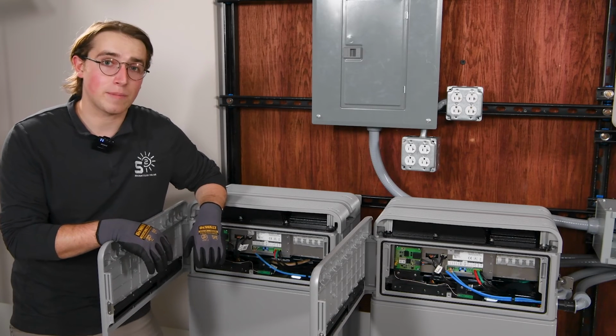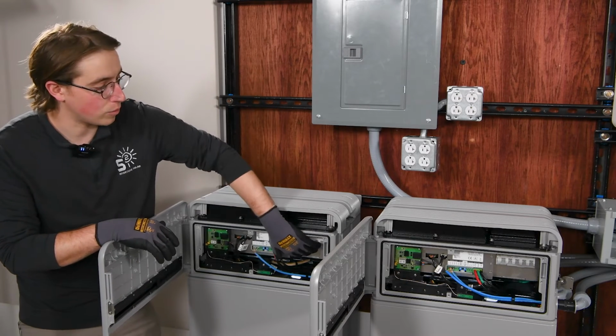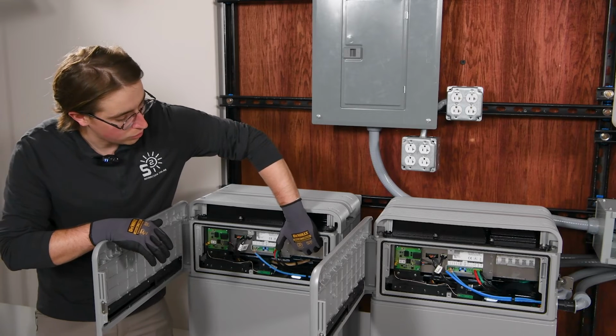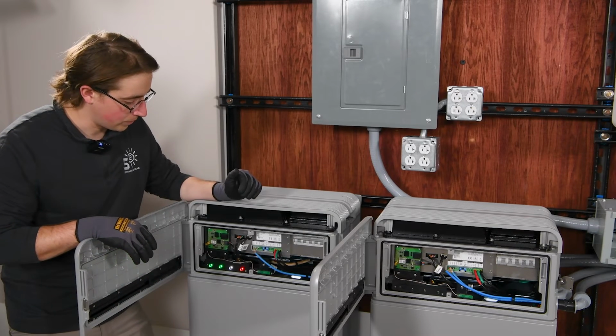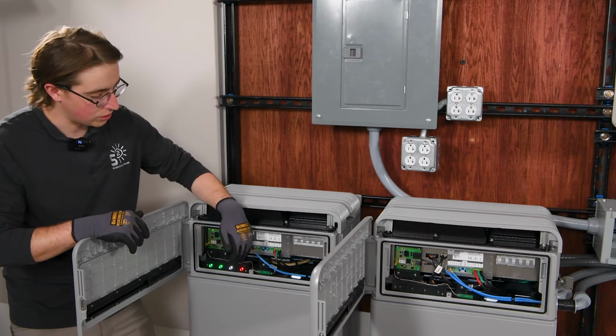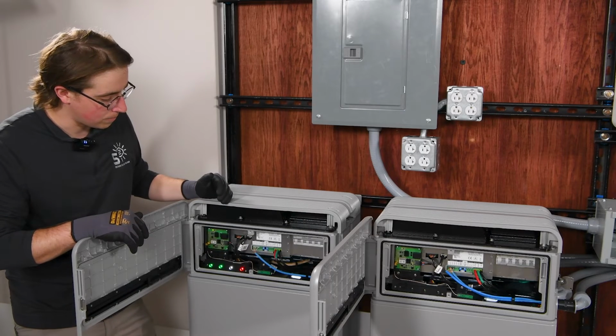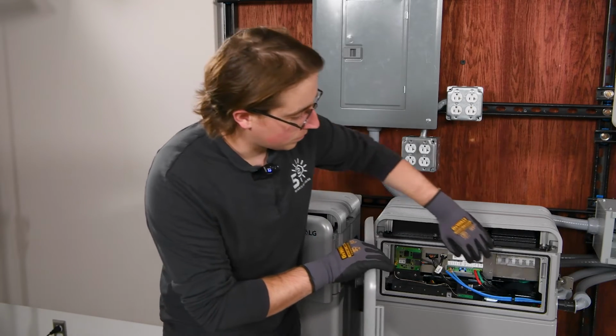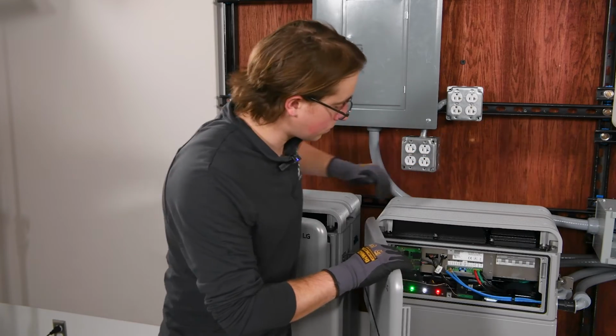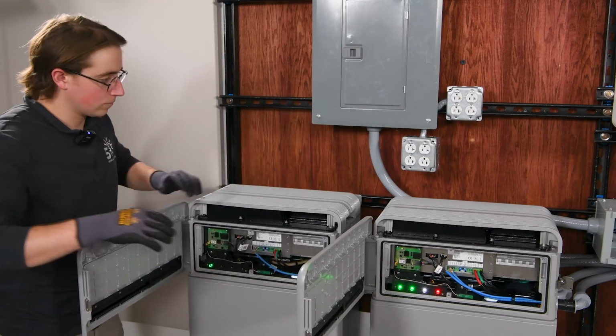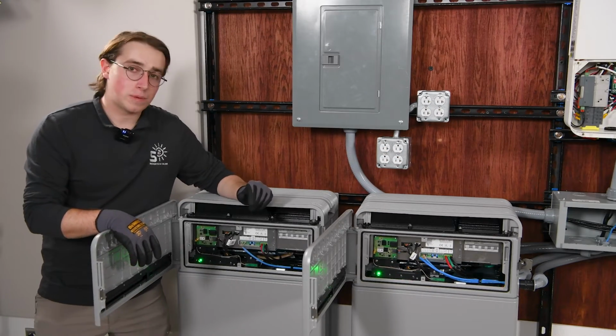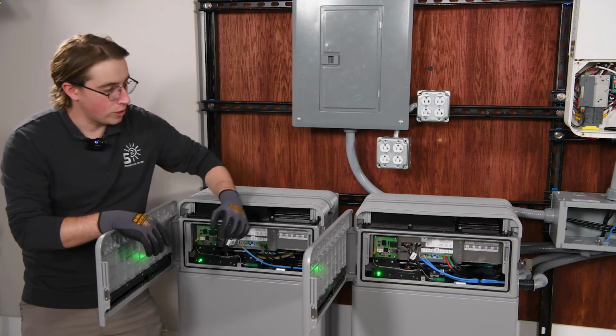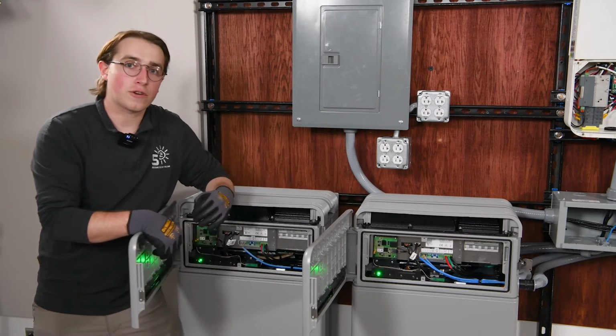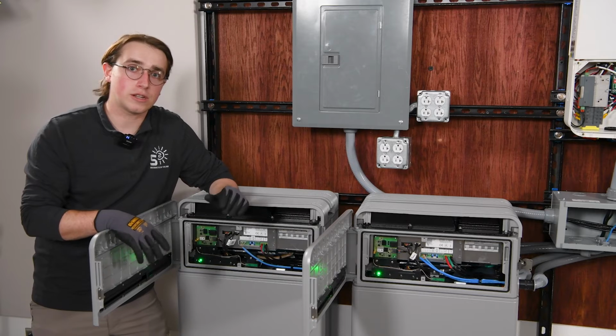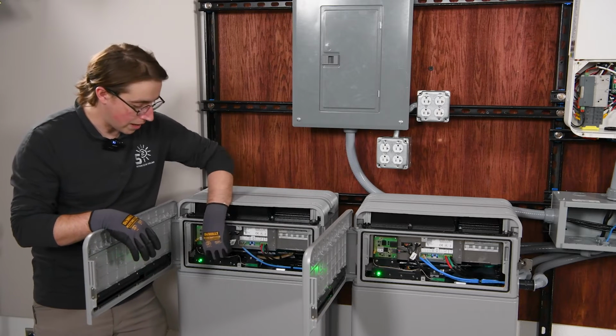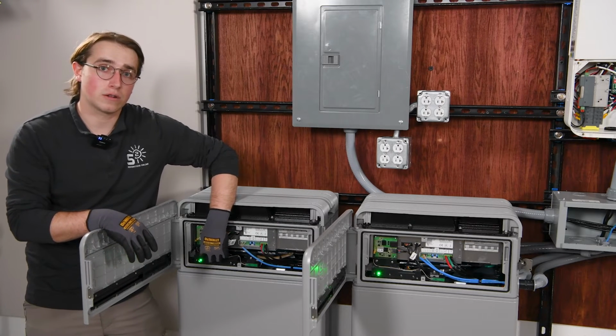So at this time, I'm going to go ahead and power on the batteries. And to do that, there's a breaker at the back that you just put in the closed position. I'll do that for both batteries, but as you can see, our LED indicators here light up. So as we can see with the batteries powered on now, we have a solid green LED on both of them. If for any reason you have to walk away from the installation during the commissioning process and you come back, make sure that you still have a solid green light.